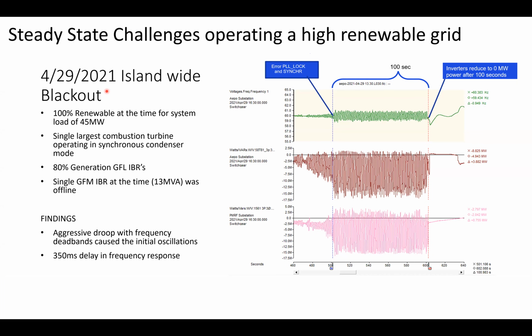Back in April of 2021, we actually had an island-wide blackout. This was due to steady state oscillations that were occurring. We were running 100% renewable at the time. System load was 45 megawatts. And what was the trigger of the event was actually found out where we were just oscillating between our grid following inverters and our synchronous machine generation that was online.